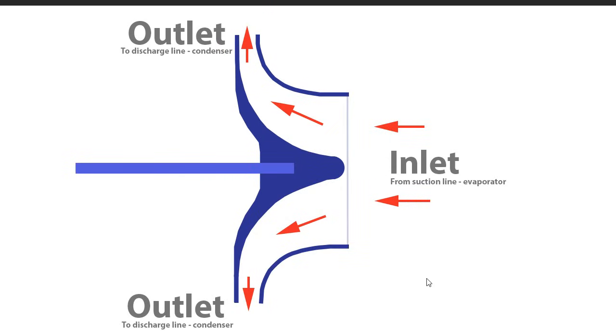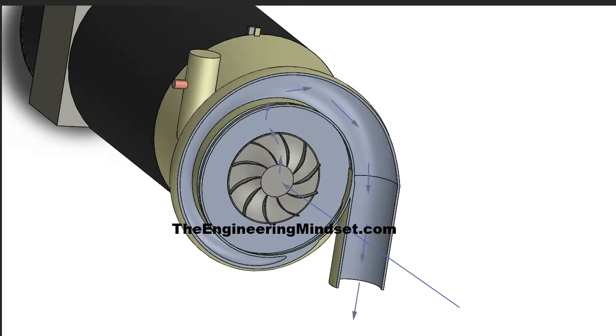So if we looked at the impeller from the side view, just to make you understand, so the refrigerant would be sucked in from that top area, and then it's going to flow through these channels and then out towards the diffuser. So it comes in from the evaporator in through the suction line, and then gets forced in, split up into multiple sections inside the impeller, and the blades then compress this and throw it out and send it off down at a high velocity out towards the condenser. So as you can see, the refrigerant coming in there, hitting into the blades. I've just done a section view on there so the blades aren't in full, and it will take this path and then make its way out through the diffuser into the volute, and then out into the discharge line.